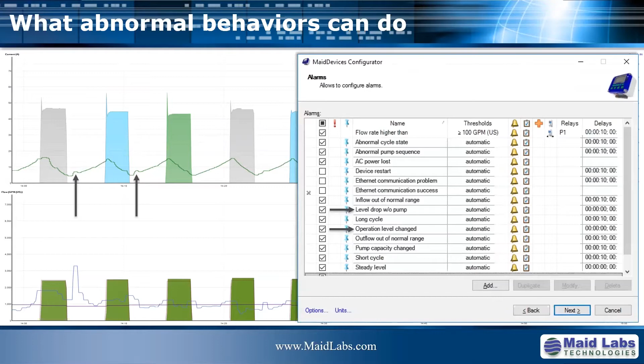These are the kind of things we detect automatically in the configuration of our instrument, how in our software we analyze every cycle. When you have cycles that alternate, it's not because it's alternating that it means it's normal. What you see here is pump 3 started, ran for 2 seconds, then stopped. Then they alternate normally, then this time it's pump 2, and this time it's pump 1. So you need to be able to analyze abnormal behavior, and this is what we've done in our software. You look at a bunch of cycles, and then you zoom in and see there's something really odd going on.